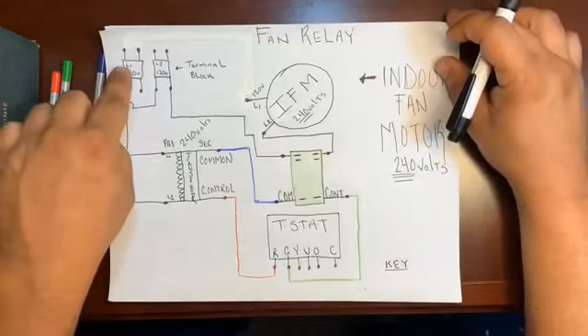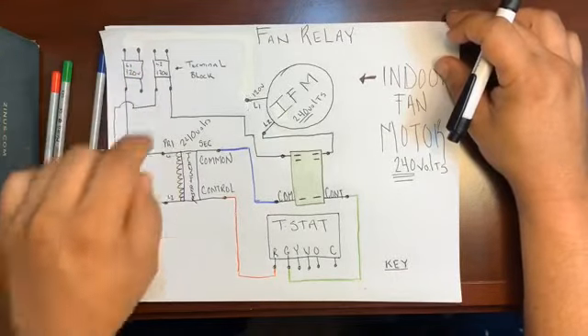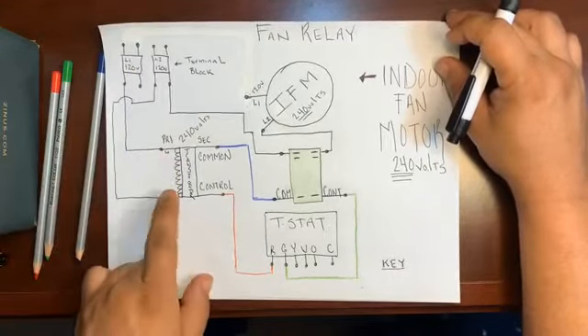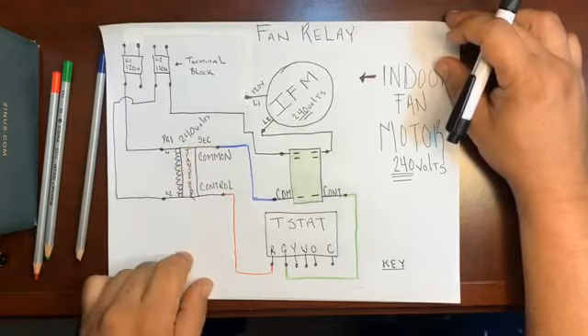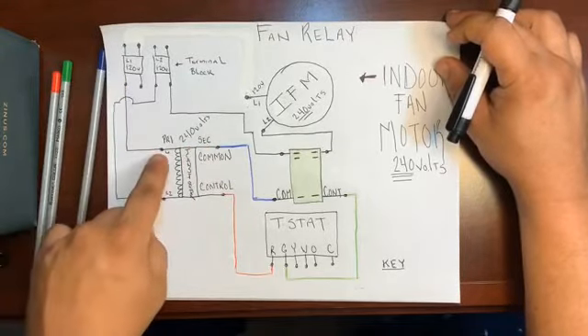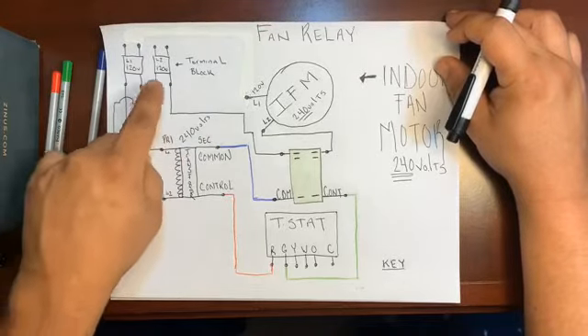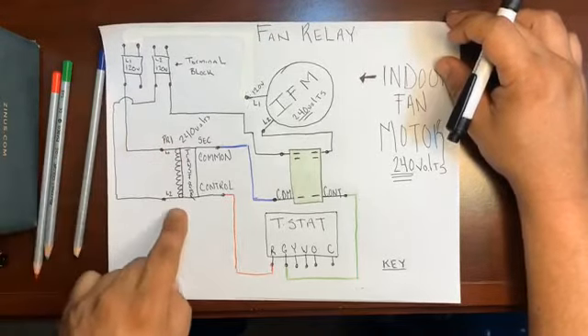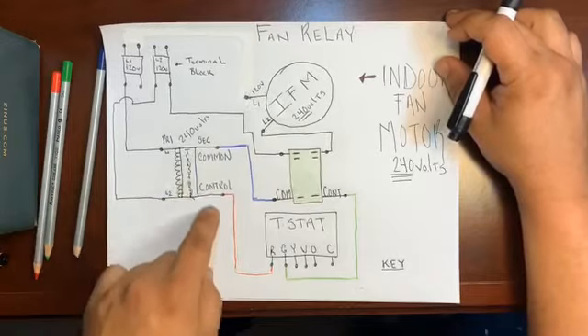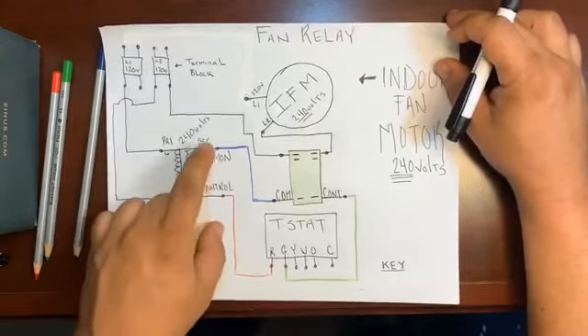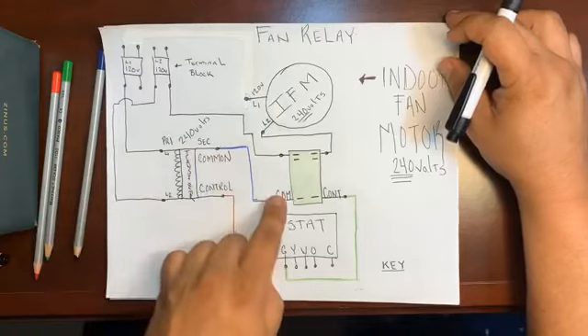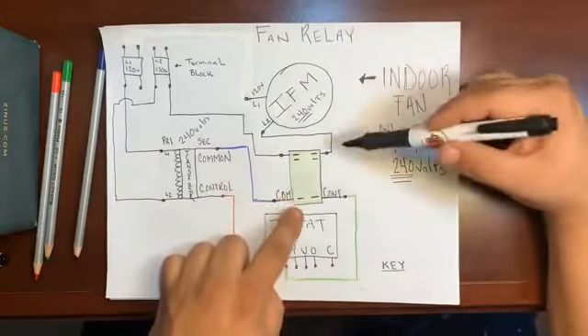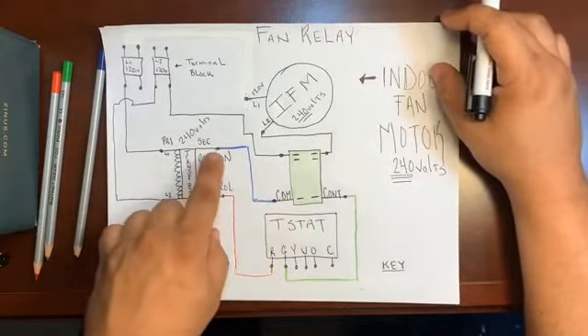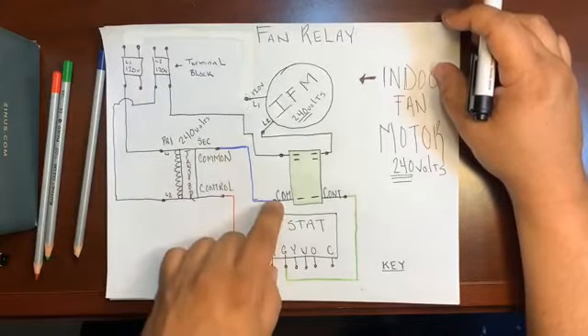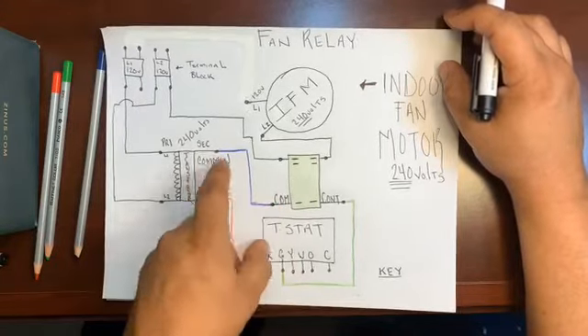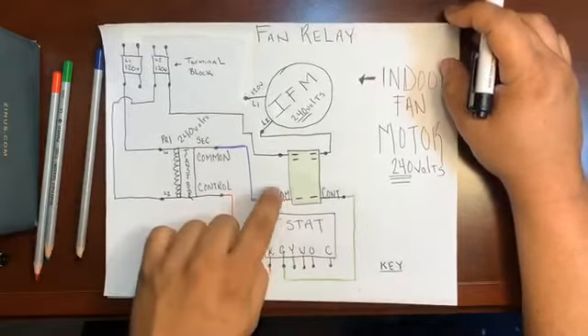Of course, we'll start with L1, L2, 120 volts on the terminal block. Our transformer with our primary and our secondary side shown. L1 coming to L1, giving it 120 volts. L2 coming down to L2, providing 120 volts. Now we have 24 volts on the secondary side. From here, the common will go in every common hand of every relay we have. Today we have a fan relay, so today our secondary common low voltage is going straight to our fan relay common, because the common always goes where? In the hand. Feed that hand.